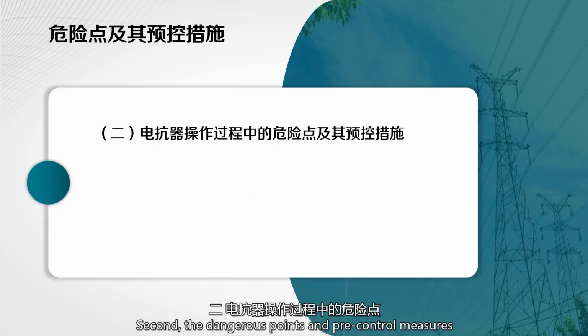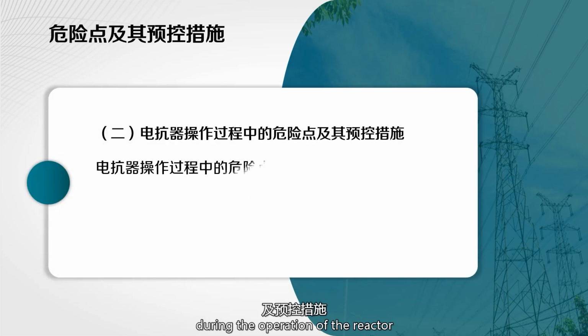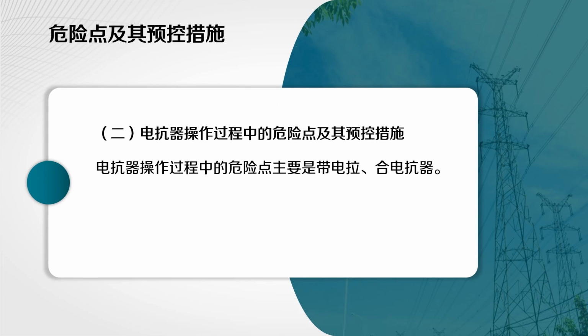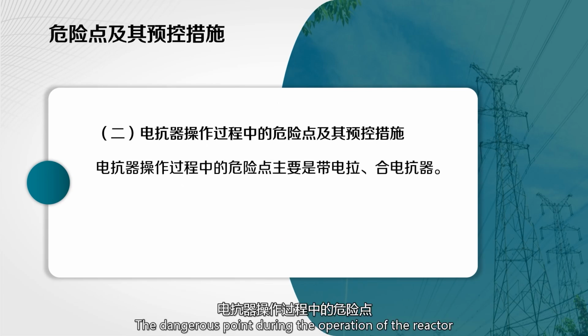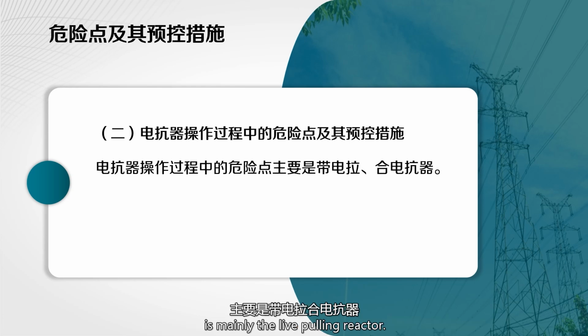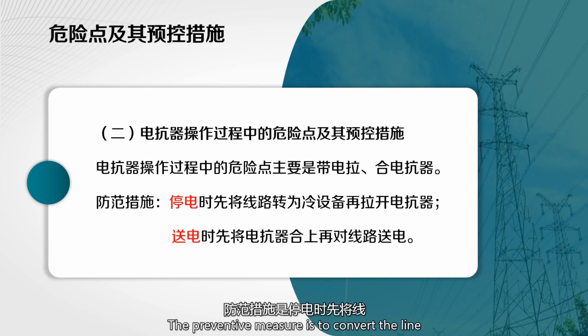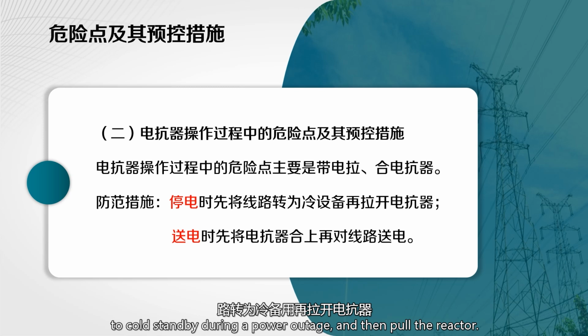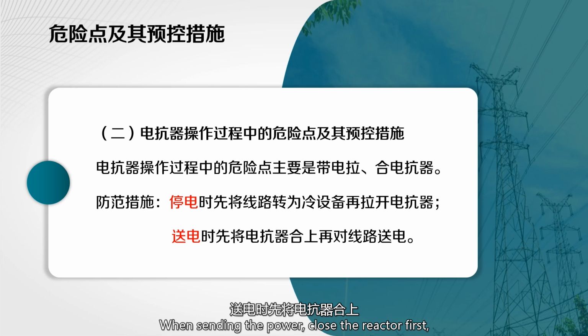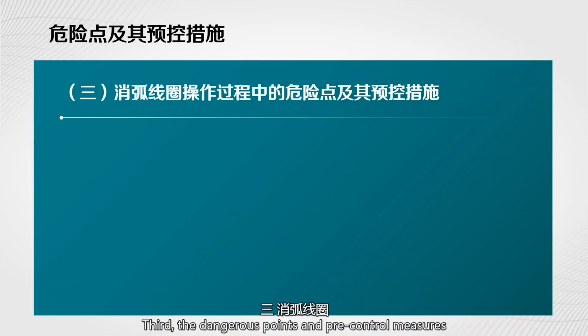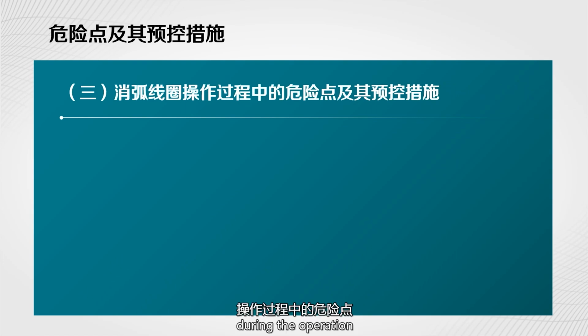Second, the dangerous points and preventive measures during the operation of the reactor. The dangerous point during the operation of the reactor is mainly live pulling of the reactor. The preventive measure is to convert the line to cold standby during a power outage and then pull the reactor. When sending the power, close the reactor first and then send power to the line.